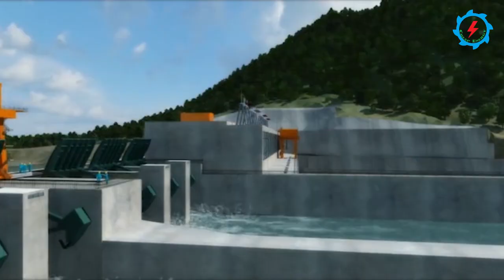The crest elevation is 592.4 meters. A total of 9 bays have been proposed in the dam structure: 5 gated overflow spillways and 4 low-level outlets for sediment sluicing as well as for augmenting the release capacity of the overflow spillway. A 29-kilometer-long reservoir will be generated upstream of the 88.4-meter-high dam, starting from the tailrace of the Kahala Hydropower Project, with an estimated capacity of 139.6 million cubic meters.